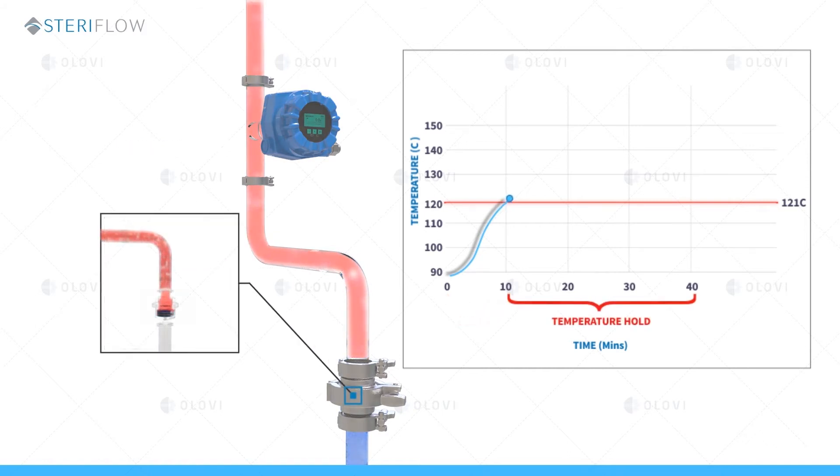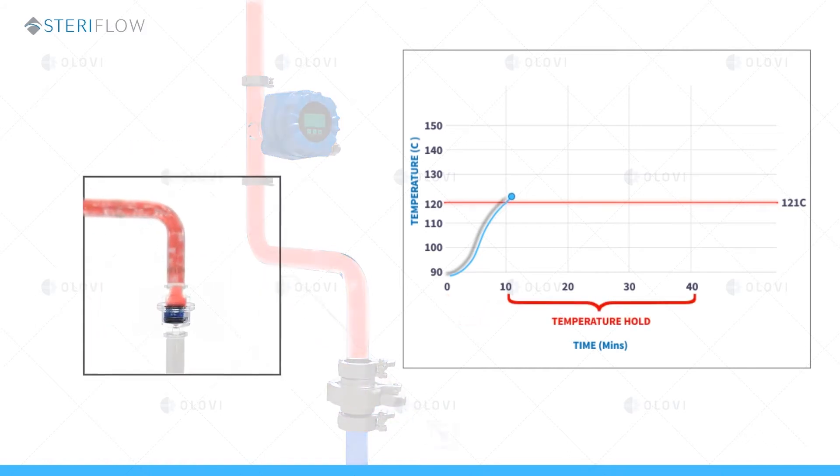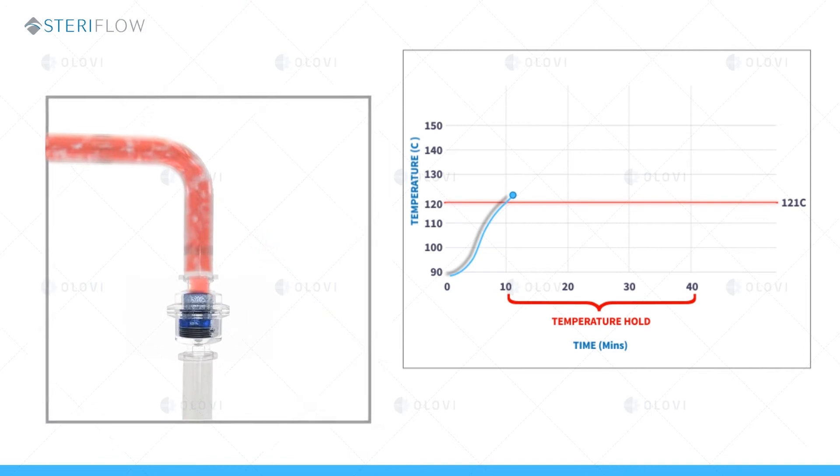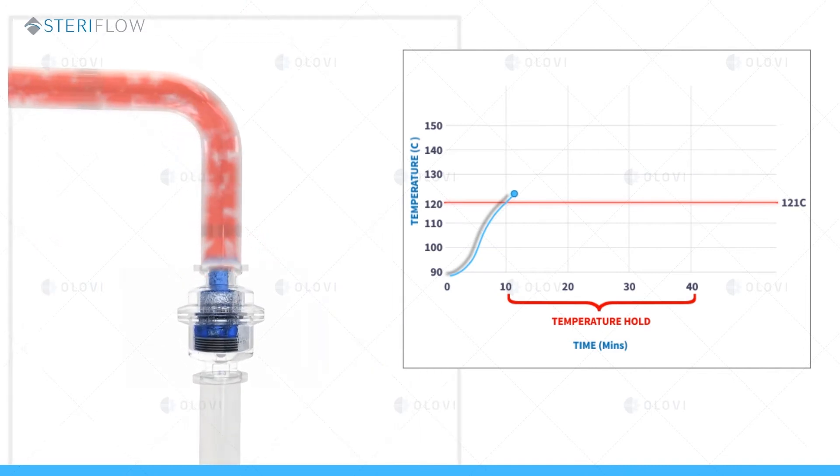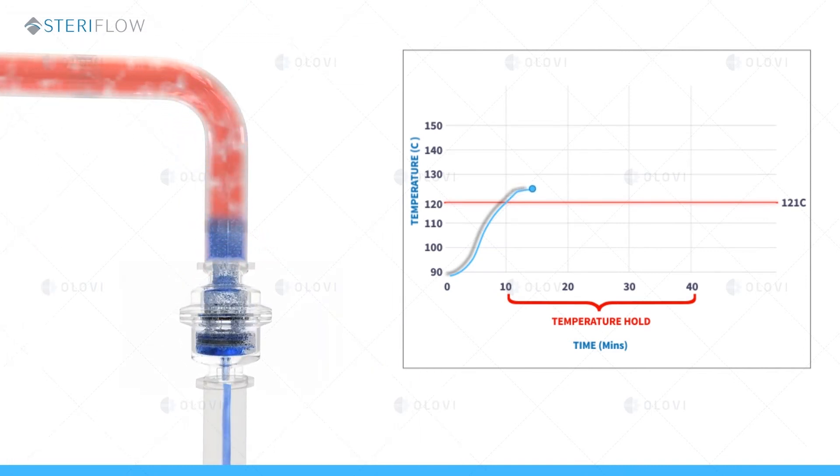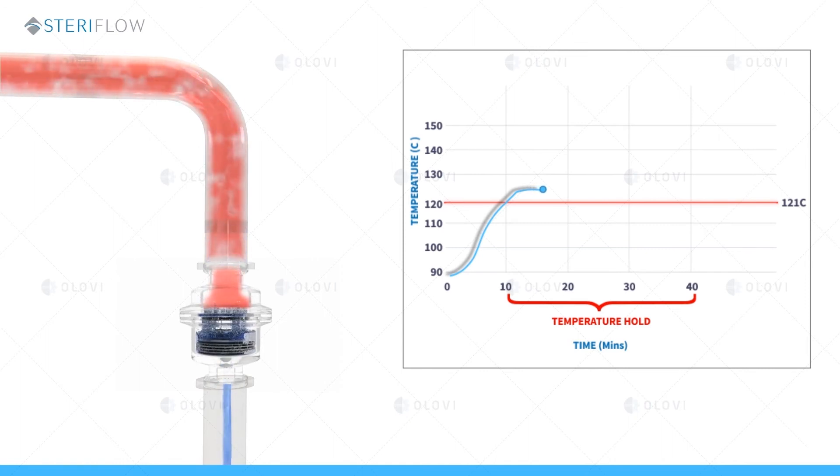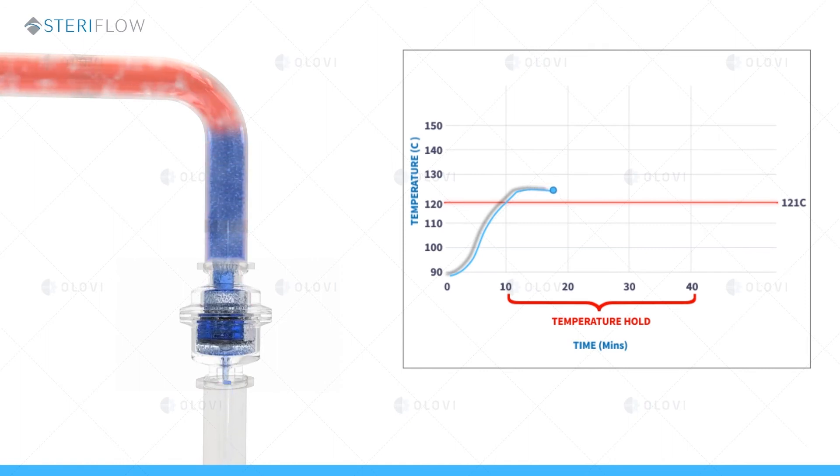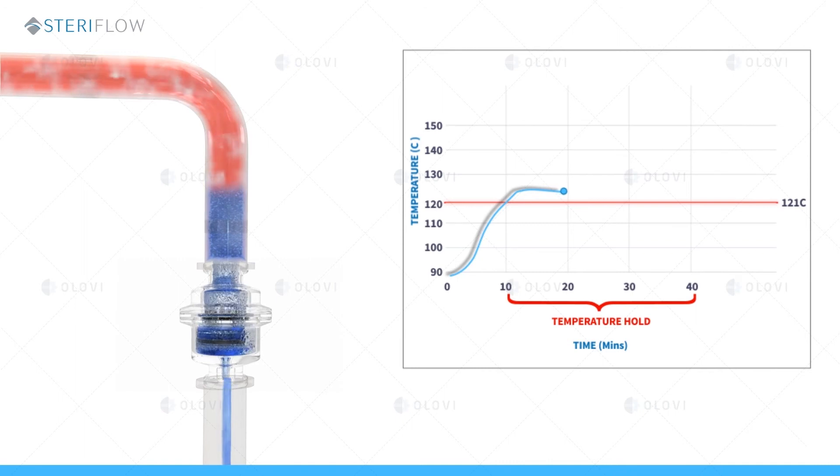Once the temperature of the vessel reaches 121C, it's important that condensate never backs up and contacts the validation temperature sensor for the next 30 minutes. If it does, the cooler condensate will cause a temperature alarm invalidating sterilization.